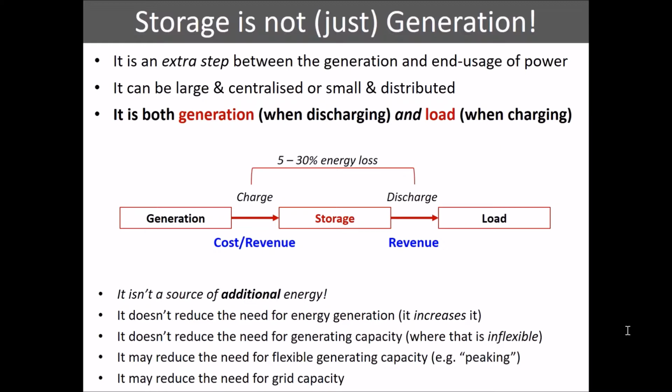You can also have it as a source of load that you can turn up if need be or turn down if need be. So in that sense, that places storage in a rather different and rather unique market segment compared to, for example, a diesel generator or a gas peaking power plant, because it has some extra advantages. Depending on the technology, it can be very, very quick to react, but also it can react in both directions. It can provide more power, but it can also suck power out. It can increase the amount of demand if that's a desirable thing to do, for example, when you've got too much wind.